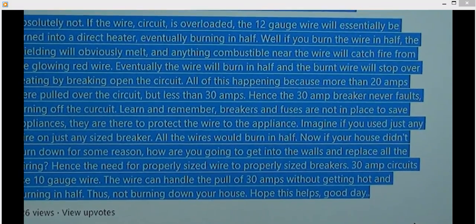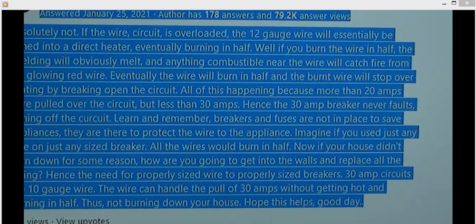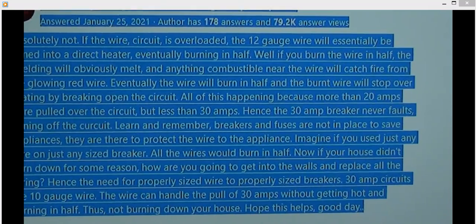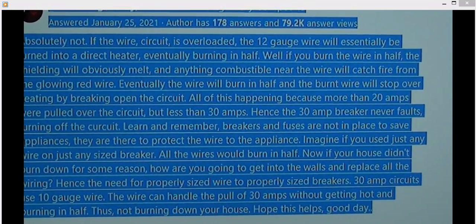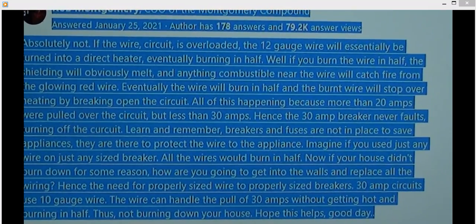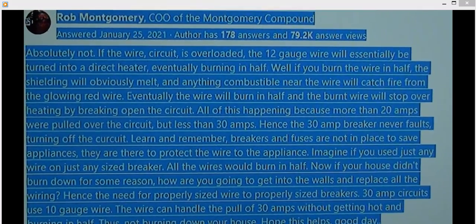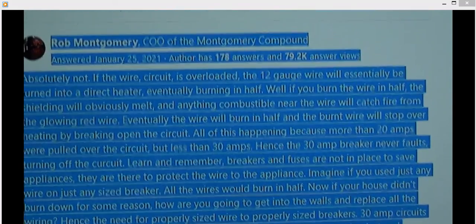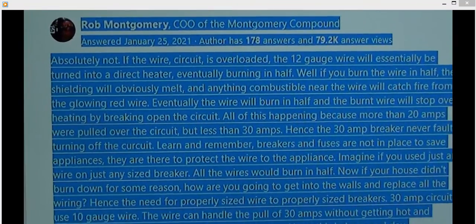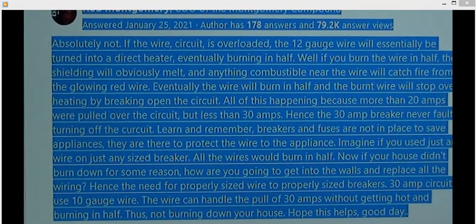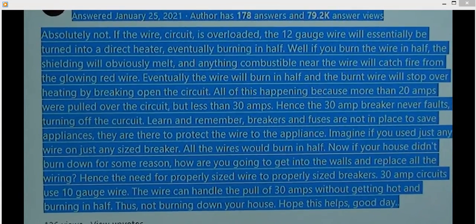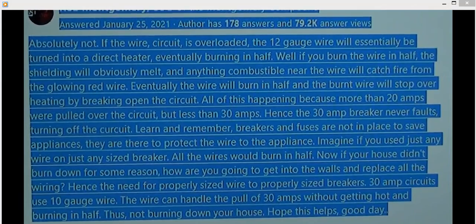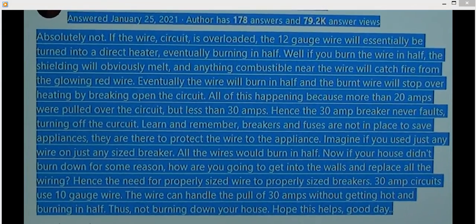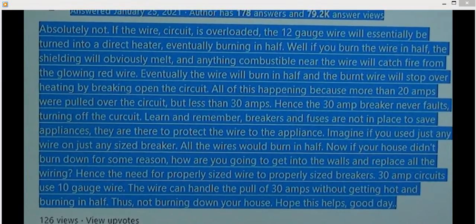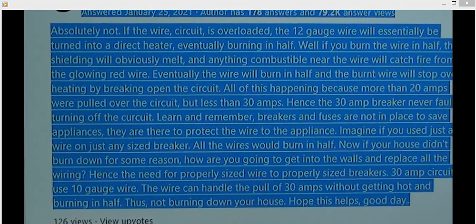Learn and remember, breakers and fuses are not in place to save the appliance. They are there to protect the wires to the appliance. Imagine if you used any wire on just any size breaker, all the wires would burn in half. Now, if your house didn't burn down for some reason, how are you going to get into the walls and replace all the wiring? Hence, you need the proper size wire to properly size the breakers.